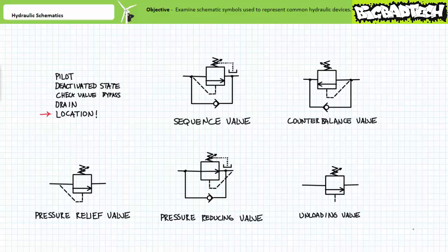Finally, and most importantly, very often the location and perceived function of a pressure control valve is a dead giveaway about the valve's true nature. Pressure relief valves are always between a pump and a tank. Unloading valves are also known to loiter around the pump. However, they're easily distinguishable from a pressure relief valve since their pilot passage isn't internal to the valve, but rather a remote external connection. Sequence valves are known to hang out around the input of actuators, as do pressure-reducing valves. They're distinguishable from one another since sequence valves are normally closed and pressure-reducing valves are normally open. Finally, counterbalance valves are the opposite. They normally hang out around the output of actuators. Note the terms input and output are relative in nature, especially regarding double-acting cylinders.